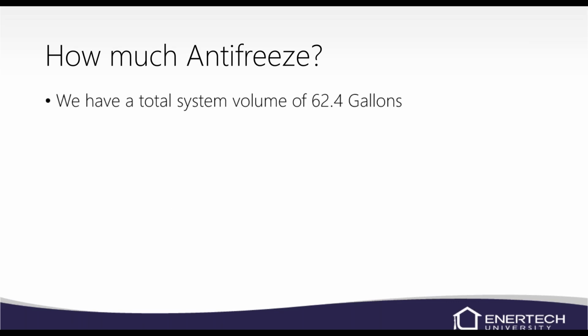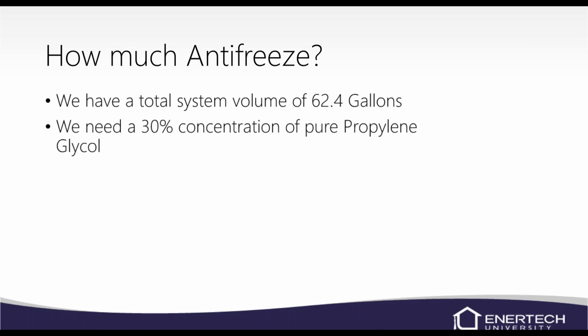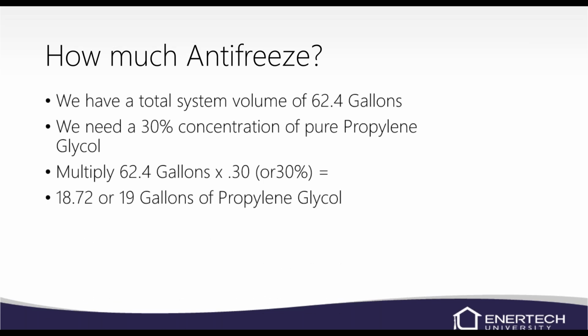So let's say we want to use a 20% methanol or 25% glycol. We're going to take that 62.4 gallons that we have for total and multiply it by the percentage. If we use 30%, multiply that 62.4 times 0.3. If we want to use 20%, we use 0.2, and so on. 25%, we use 0.25. We'll just use 30%, and that tells us 18.72 gallons of glycol is going to be needed. So you can go ahead and order that. Obviously, we don't have 0.72 gallons, so we order 19 gallons of glycol, and that'll get you covered. So you can actually figure out well before they get to the job of that flush cart how much antifreeze they need, how much they need to order.